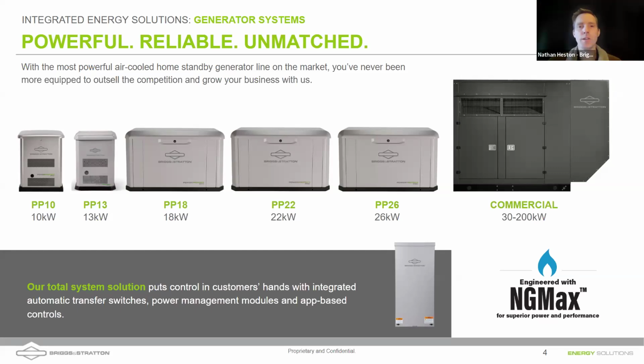What do you mean by the same power output, Daniel? You mean no derating? Yeah, exactly. A lot of people don't realize when you run a generator on natural gas, maybe a 22K generator is only going to put out maybe 18.5 kilowatts. We've optimized some of the ignition timing, the exhaust manifold, the intake manifold, so that whether you're running on propane or natural gas, you're still going to get that nameplate rating. That's not true with many of our competitors, so we're pointing this out, so you're comparing apples to apples when showing customers products and options for whole home backup.